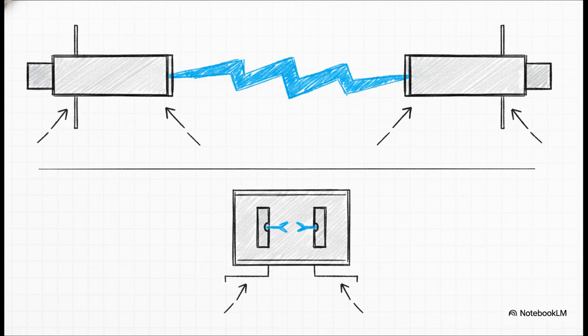So why do we deploy gas-insulated switchgear at the absolute highest voltage levels? Well, it all comes down to the exceptional dielectric strength of that SF6 gas. You see, at extreme transmission voltages, we're talking 400 or 230 kilovolts, an electrical arc desperately wants to jump massive distances through the air. SF6 gas stops that dead in its tracks. It dramatically shrinks transmission-level clearances compared to traditional air-insulated designs. To put that into perspective, if Singapore tried to use conventional air-insulated yards for these transmission stations, they'd need roughly 5 to 10 times more land area. So GIS isn't just a nice-to-have preference here, it's an absolute geographic necessity.